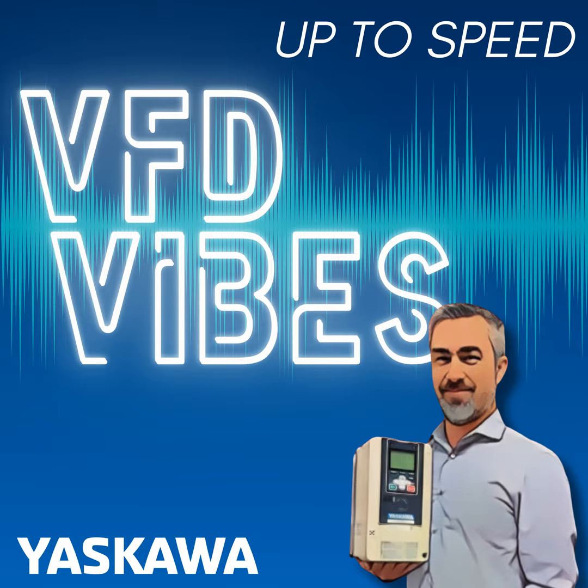Now, let's say I put a variable speed drive on this with a typical PWM output. And remember, we discussed a little bit about parasitic capacitances. There's capacitance from everything to everything else. There's capacitance between the leads running from the drive to the motor, and these leads are fed with a pulse width modulated voltage.